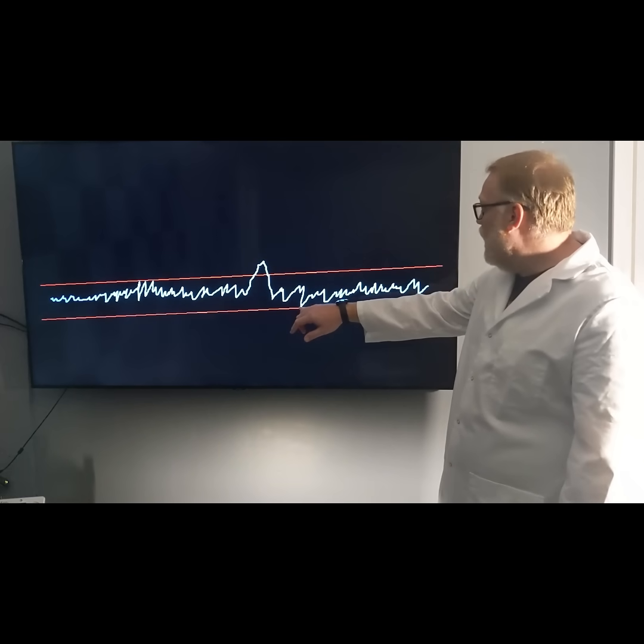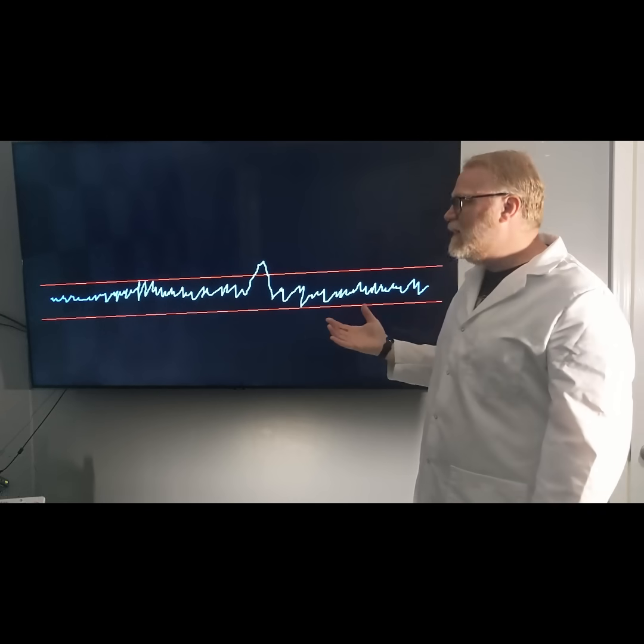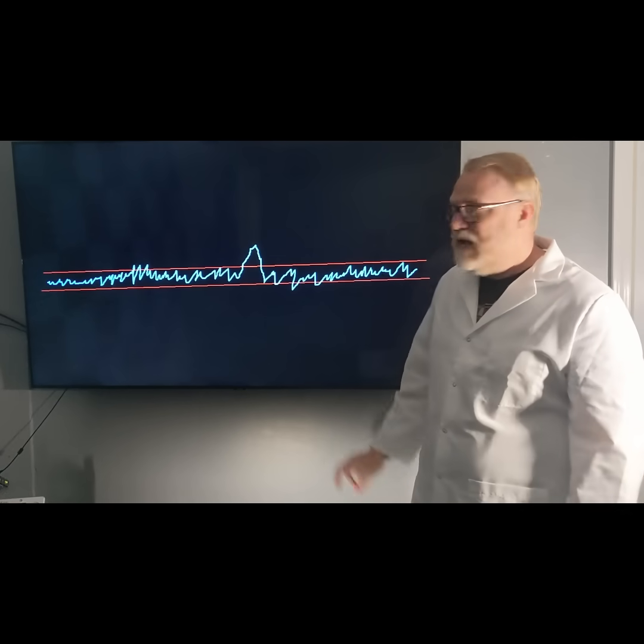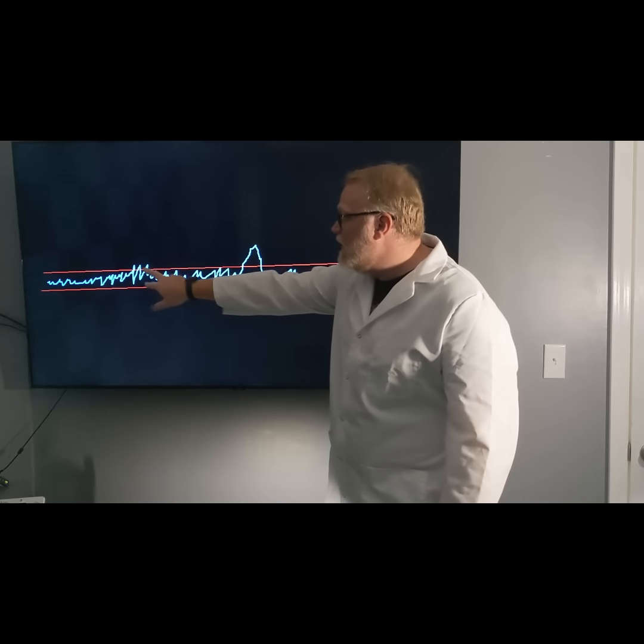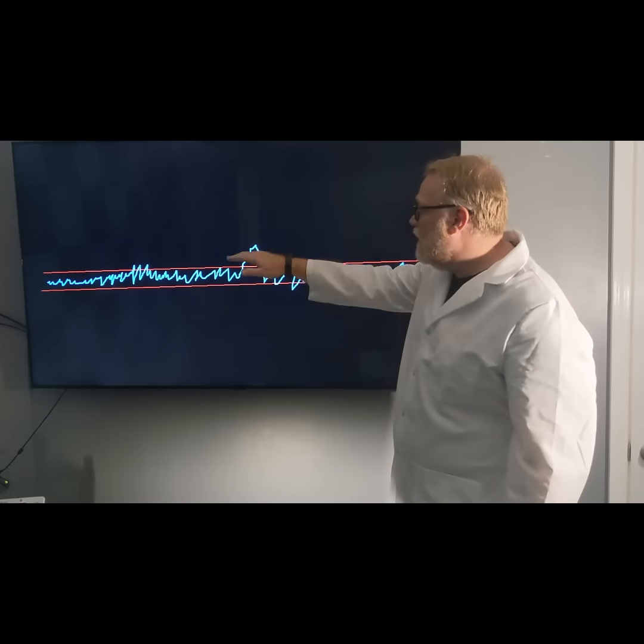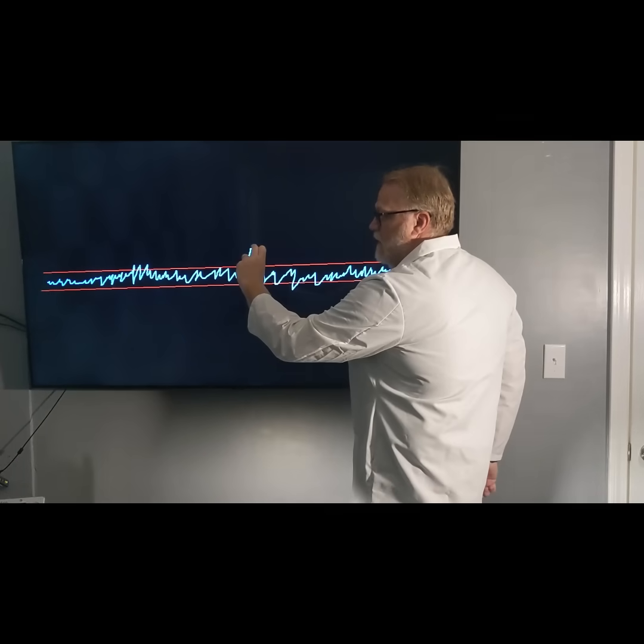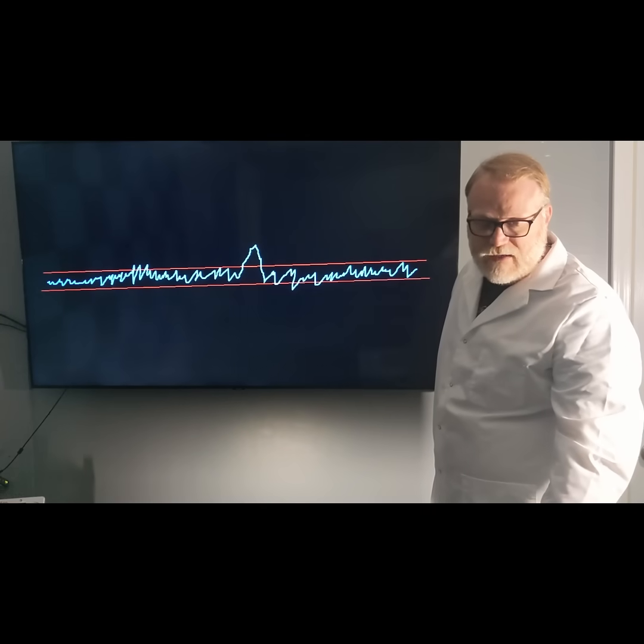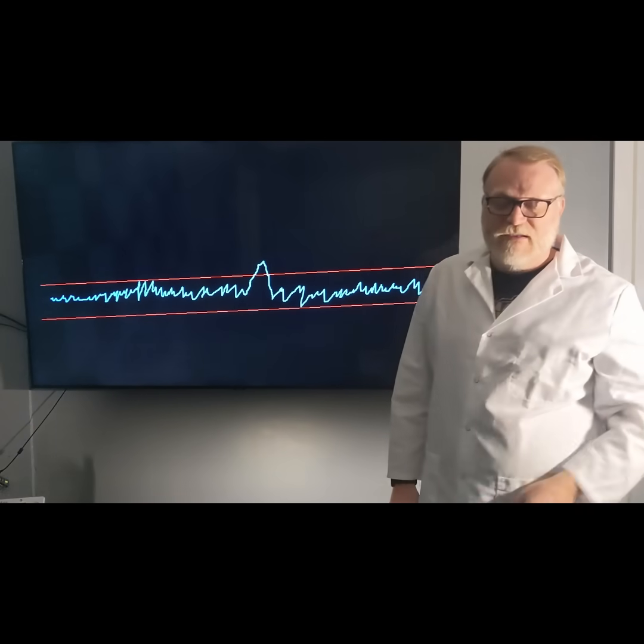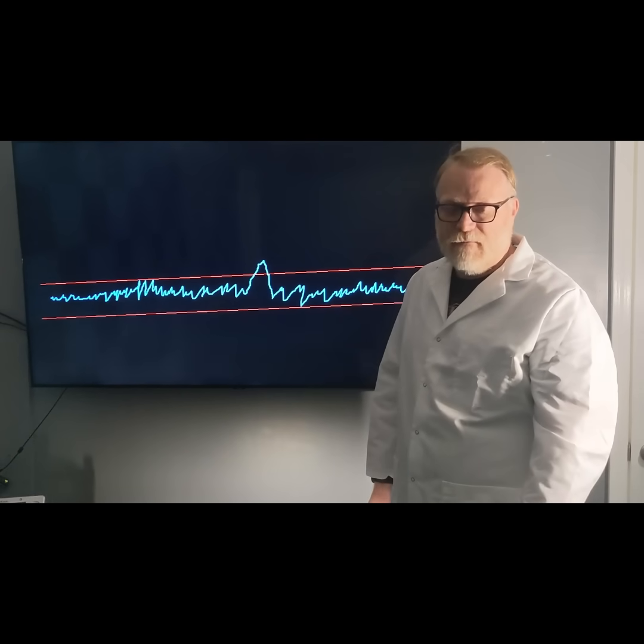If we take a look, we have a low point there and three high points in a row right there. We could say that's our noise, but most of the noise doesn't fall within that — it's a lot closer together. So we take a look and measure what we call core noise, ignoring some of the outliers, but most of the noise falls within there. Our reading of our peak is actually measured from the center of our noise. Depending on where that center sits, the peak measurement can look larger or smaller, so they do give two different answers. How you measure your signal-to-noise is going to open up some challenges.